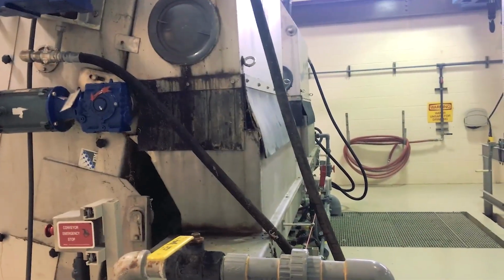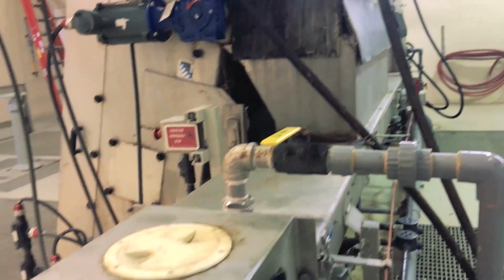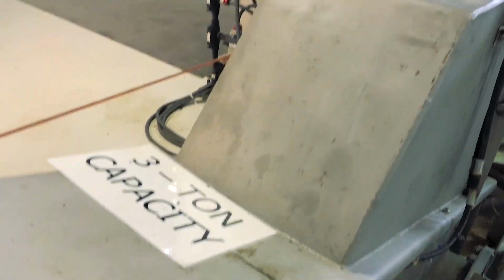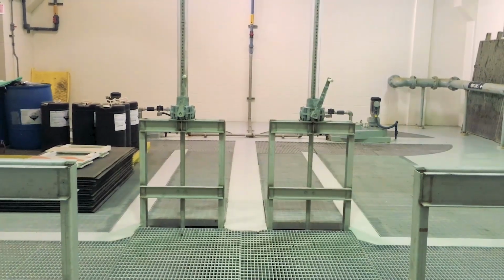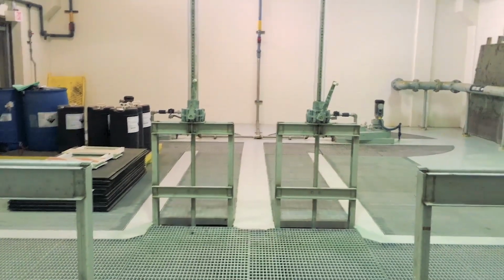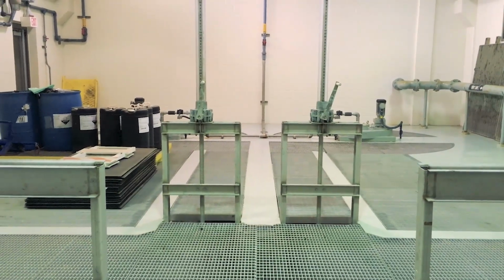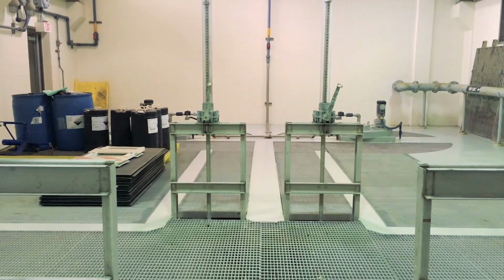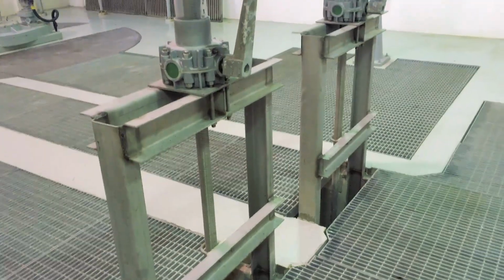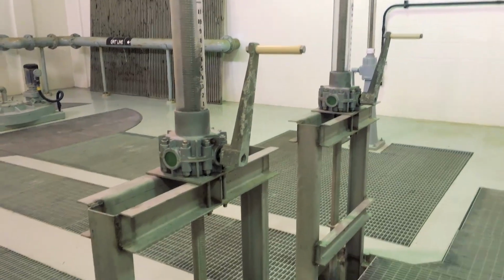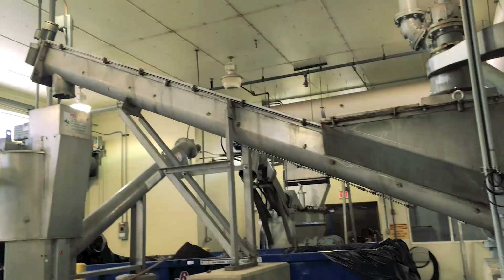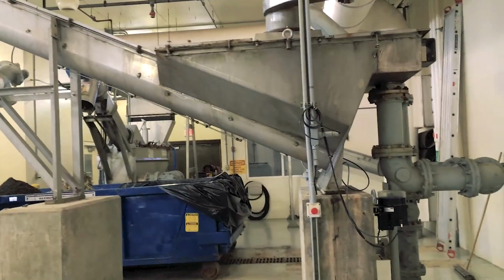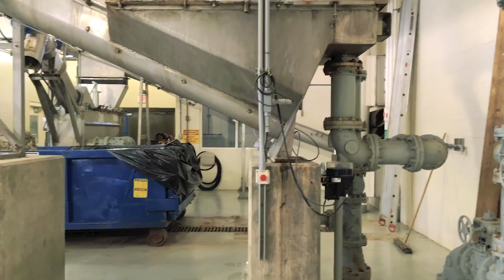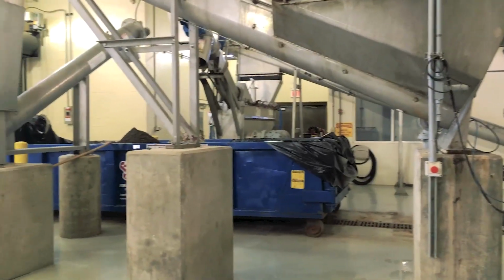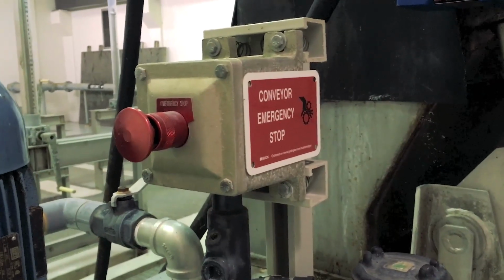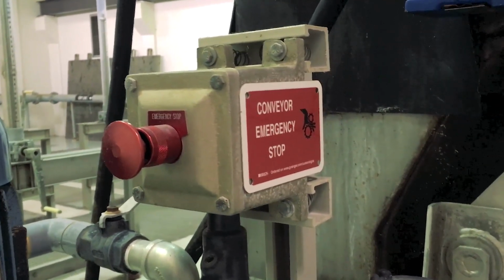The solids removed from the waste stream are sent to an automated solids processing station, which includes conveying, washing, and compaction units. Grit removal follows the screenings process and is carried out in 2 concrete basins called grit traps. Non-potable water is also extended to the lower grit hopper to flush and suspend settled grit solids. The settled grit from the traps is called slurry, a mixture of wastewater, inert solids, and organic materials. This slurry is passed through a cyclone separator, a grit classifier, and a grit washer. The washed inert solids are deposited into dumpsters by a shaftless screw conveyor. The screened and degritted wastewater flows to the primary lift station for primary treatment.